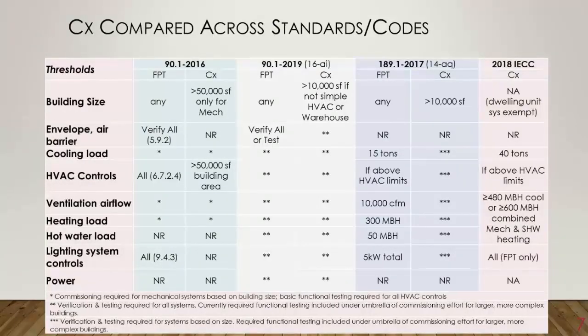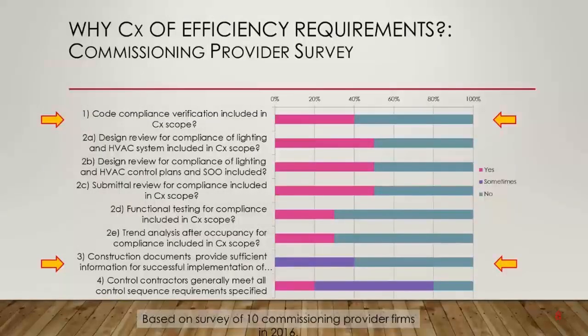Now, one reason we felt commissioning was important for 90.1 is we did a survey back in 2016 as part of a code controls verification. We went out to 24 buildings and actually looked at 14 different lighting measures and 10 HVAC measures, and saw how they complied with code as far as how they were installed.